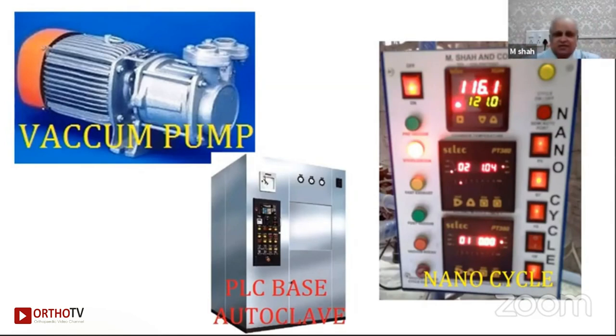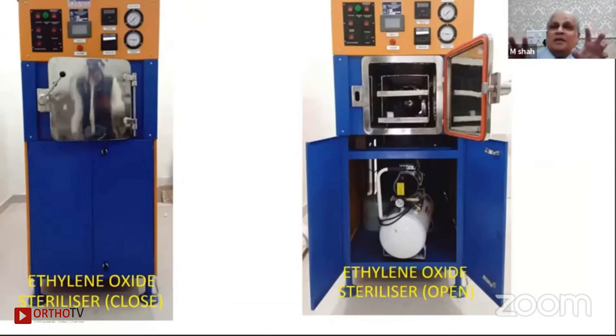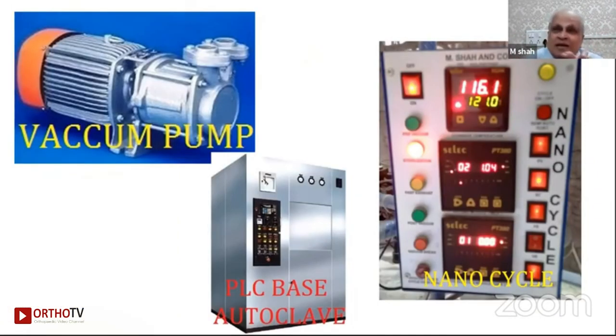Right? The procedure is very simple. You create pulsing. When there is no air in the chamber, allow the steam to enter from the jacket to the chamber. Now, when there is no air pressure, no air in the chamber, what happens? The steam that enters has 40% higher latent heat. Although the temperature is the same, there is no air, nothing to condense. Therefore, the job is done in 3 minutes.